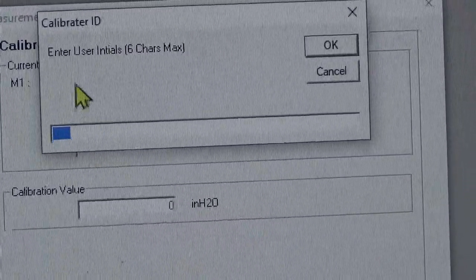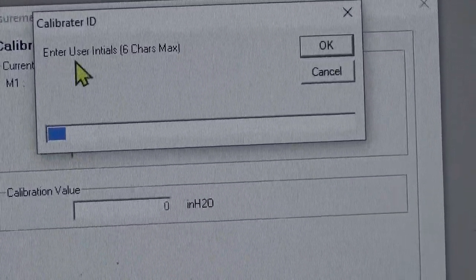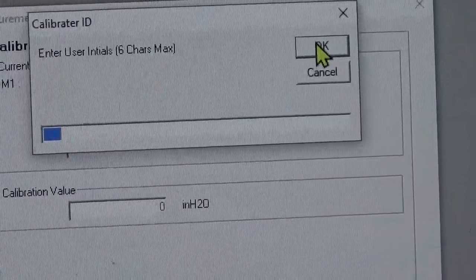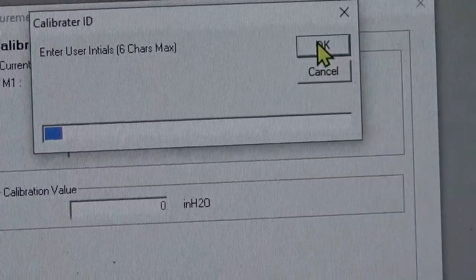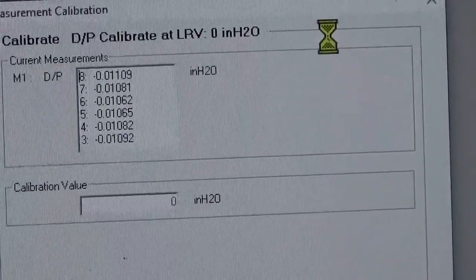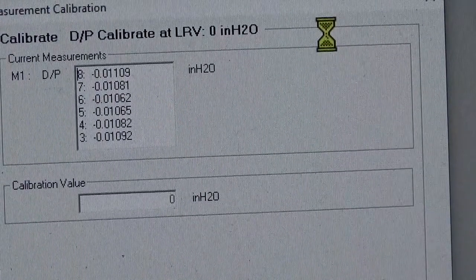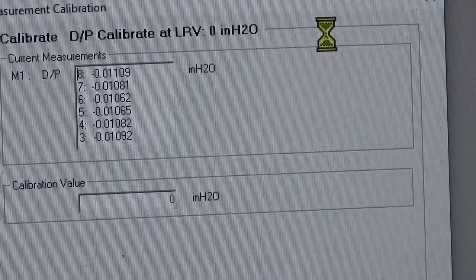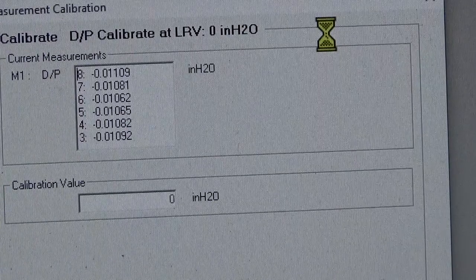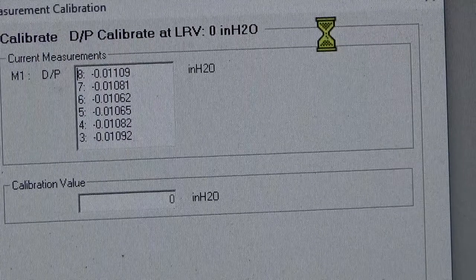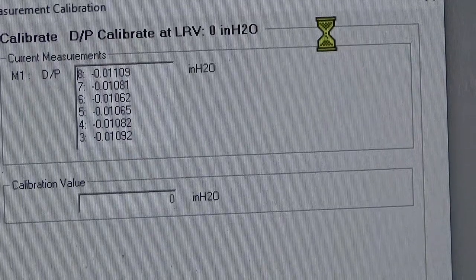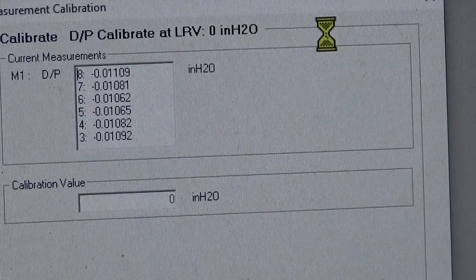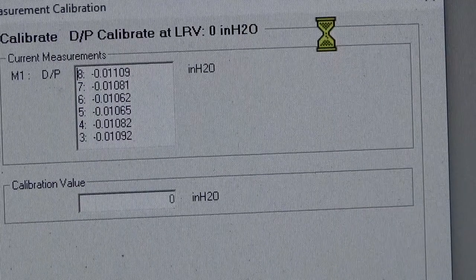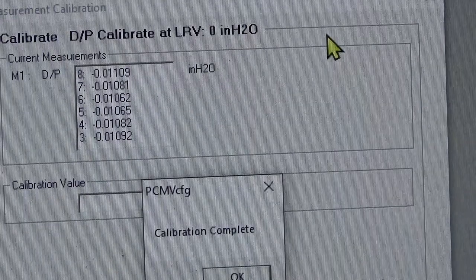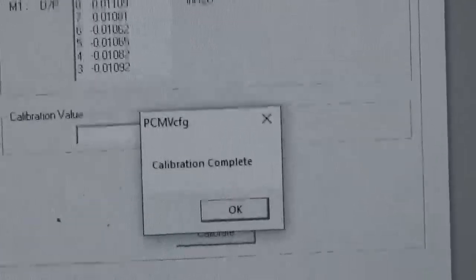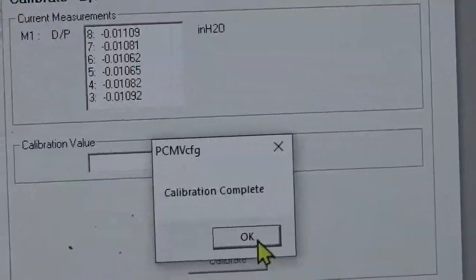It's going to ask me if I want to enter some user's initials. This is optional. I'm not going to enter any. So I'm going to say OK and leave it blank. So now at this point, the transmitter will go offline and execute the 0 calibration. This will take a few minutes, and when it's done, you should get an indication on the screen that the calibration is complete. And there it is. So I'm going to hit OK.